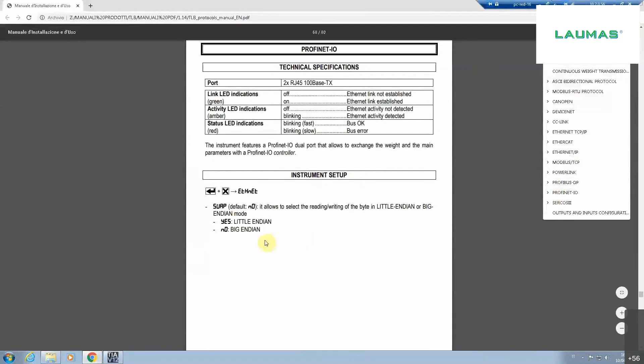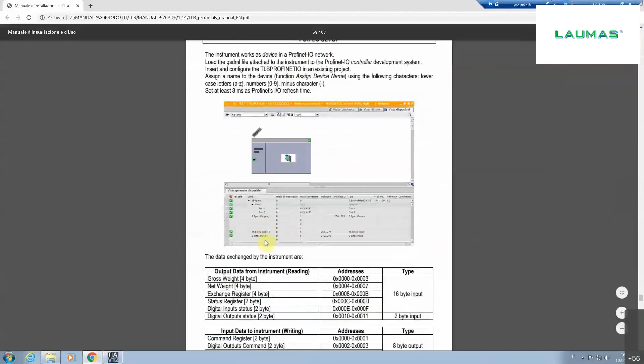Now we can use this information to define a set of useful tags that could be used, for example, during the PLC software development in order to properly manage the data exchanged with the TLB instrument. Another important set of information useful for the tag definition is contained in the protocols manual. Now we can open it and open the Profinet section. Here, after a set of preliminary information, we find these two tables that show how the data exchanged by the TLB on the Profinet network are organized.